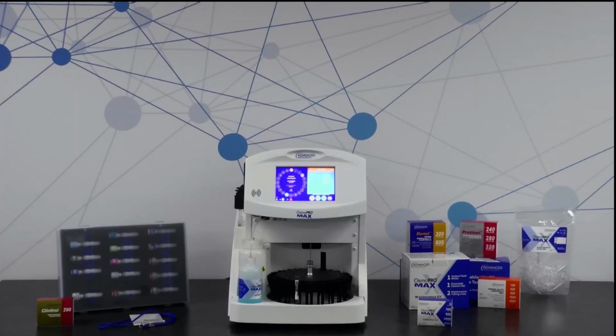Okay, is the barcode scanner similar to the A20? This is, I believe, a new piece of hardware, so it shouldn't be similar to the A20. There are two separate barcode scanners: one on board for the tubes you're loading onto the turntable, which also has a sensing mechanism underneath, and then one under the top cover of the instrument where you're actually going to scan your badge or any of the UDI codes on any of the consumables.